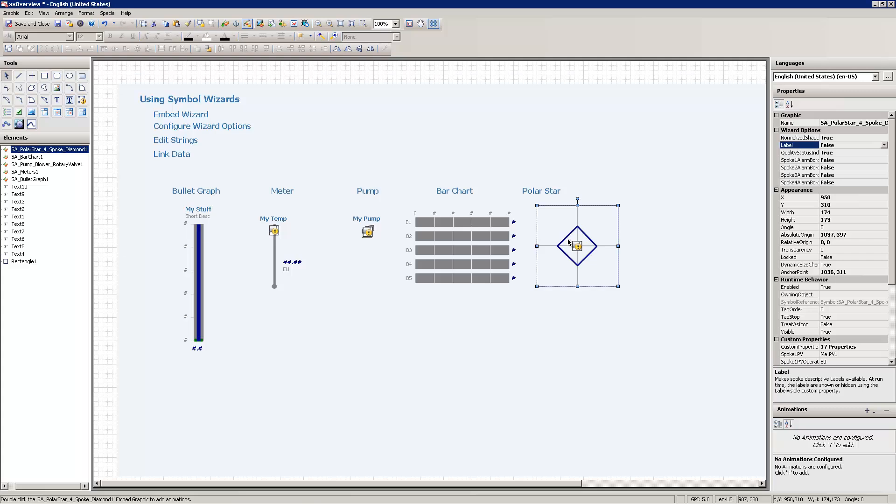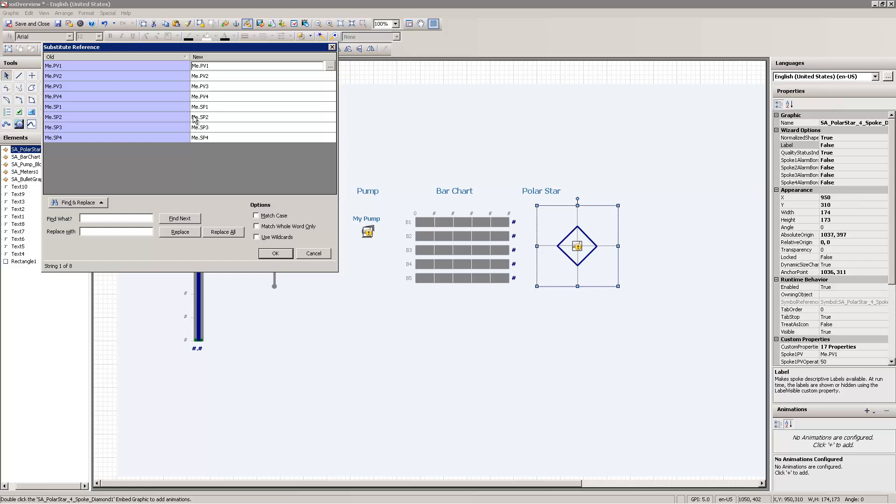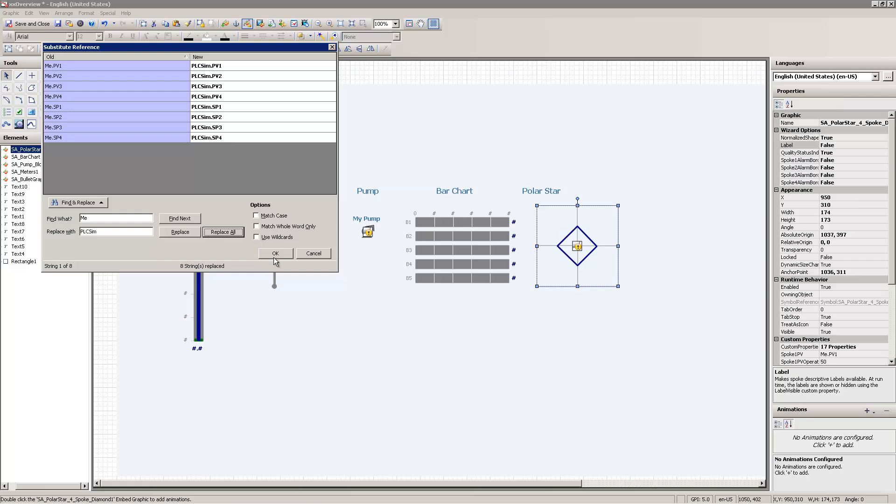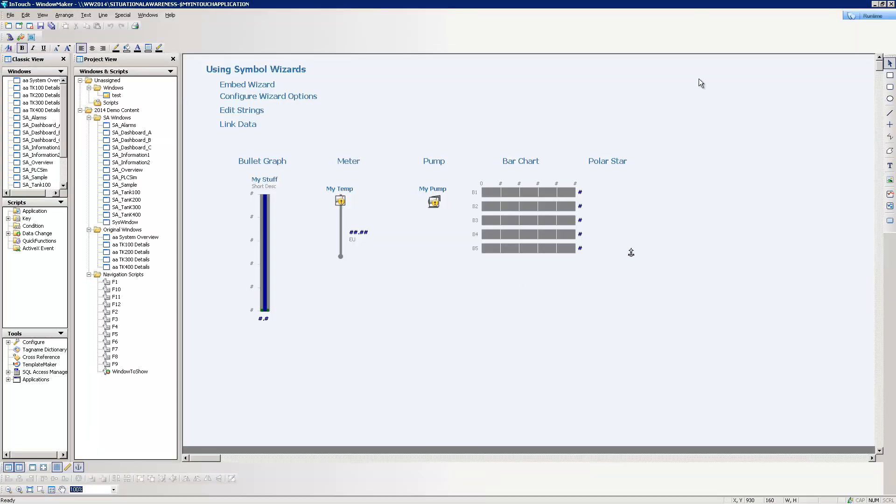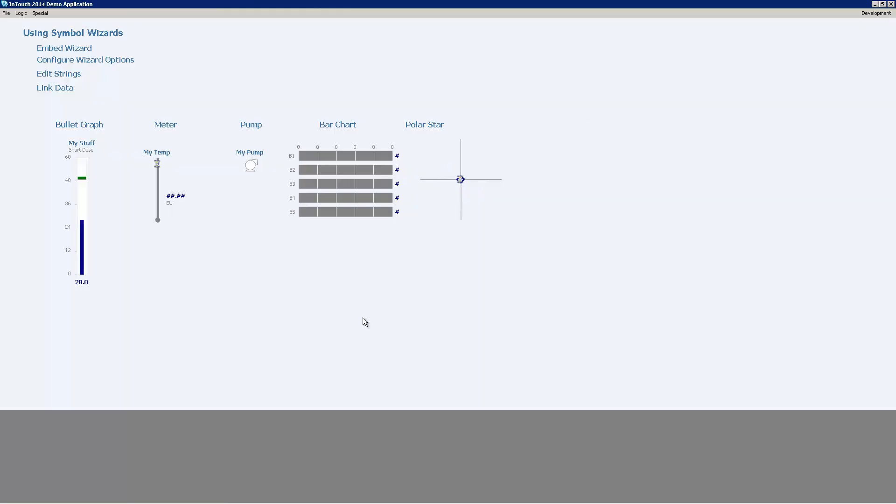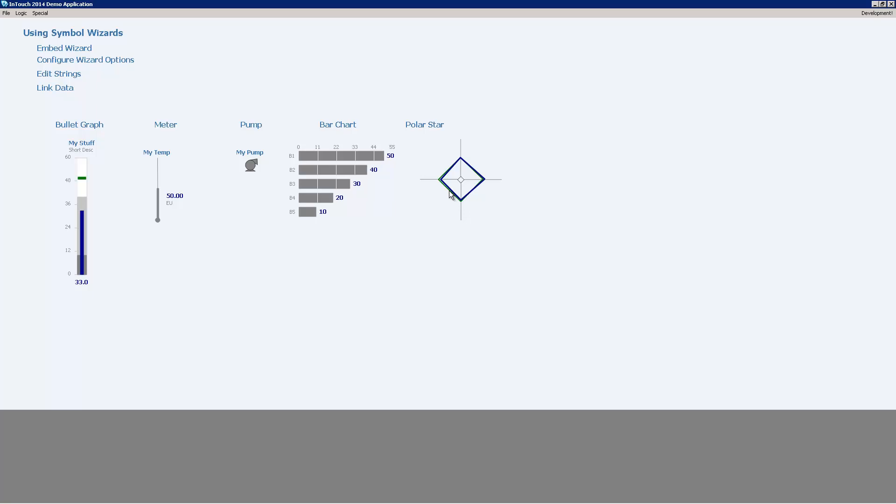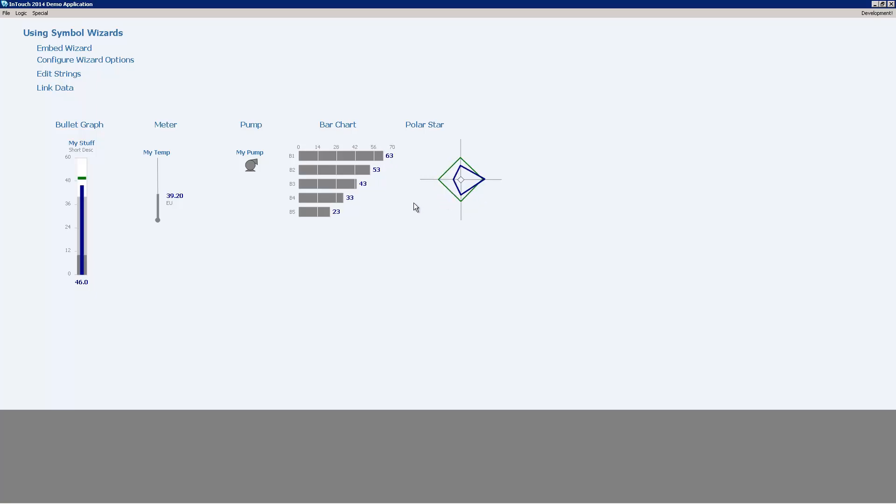And linking data. So again, remember I can link data by going into custom properties or substitute references. Control E will bring up my substitute references. So let me first select my element and hit Control E. I'm going to get rid of all these me's again. Go to that simulation object, from me to PLC sim, replace all of them. And you can see what has changed is I've got four process variables and four set points. And it's changed those out there. And now what I'm going to be able to do is hit save, go over to runtime and see this thing working. The green line is showing you the set points and the blue line is showing you the actual process variables. So again, this polar star is pretty effective to see when multi variables are starting to move away from their expected set points. I don't have to have any numbers here at all. In the case here, it didn't even have any labels. But what I can quickly see is when that has moved away. And my simulation is showing you now that you have several variable, three of the variable values were well below their set point.